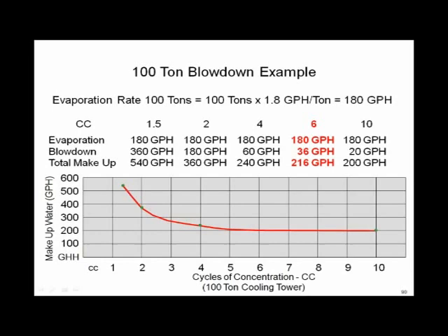Now, as I increase the cycles of concentration, what happens to the total usage of water? Notice the evaporation rate has to stay the same. Cooling towers need 15 pounds of water pretty much per ton evaporated to keep them working. That's fixed, constant. So the 180 gallons per hour evaporation rate stays the same. But as I increase the concentration, as I increase the number of rocks, the amount of water I'm blowing down goes down. So at 4 cycles of concentration, I'm blowing down 60 gallons per hour. My evaporation is still the same. My total water usage is 240.